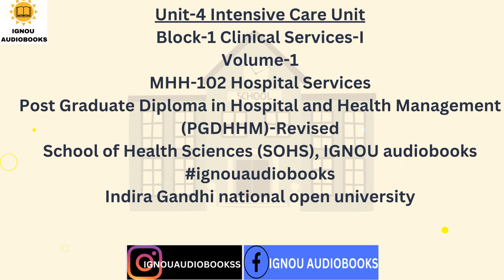Although the ICU is supplied with disposable and CSSD items, it has been felt that a small portable electrically heated pressure steam sterilizer of minimum 175 mm diameter by 300 mm length for emergency use will be of immense value for its efficiency.